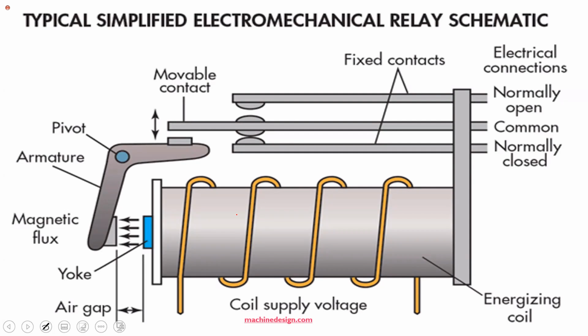All right, so for the attracted armature, just note the contact. So you have up at the top normally open and normally closed contact. And what that means, a normally closed or the name given to a contact is the condition before it is energized. All right. So, or the unenergized state of the contact. So without any action on the contact, the normally open means that it is open. And normally closed means that it is closed.